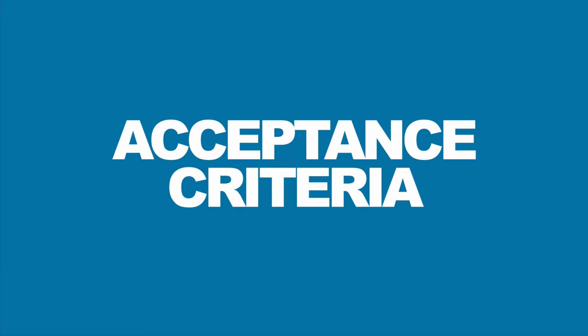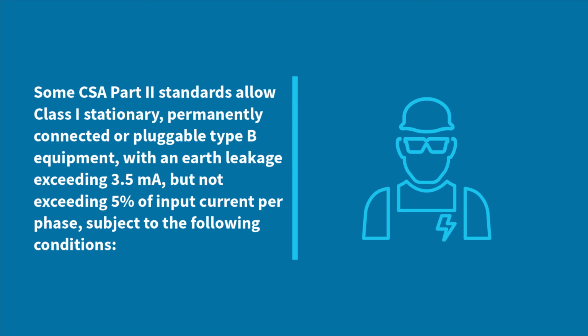Acceptance criteria. Some CSA Part 2 standards allow Class 1 stationary, permanently connected or pluggable Type B equipment with an earth leakage exceeding 3.5 milliamps, but not exceeding 5% of input current per phase, subject to the following conditions.